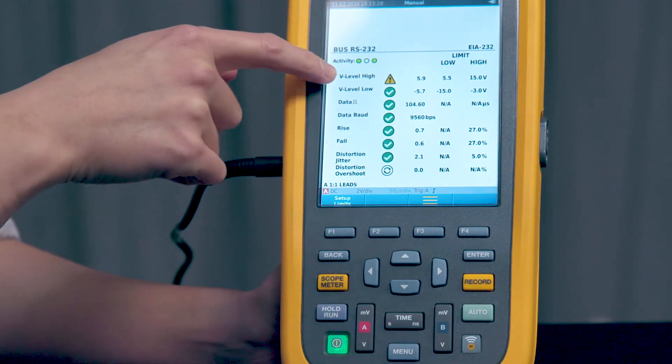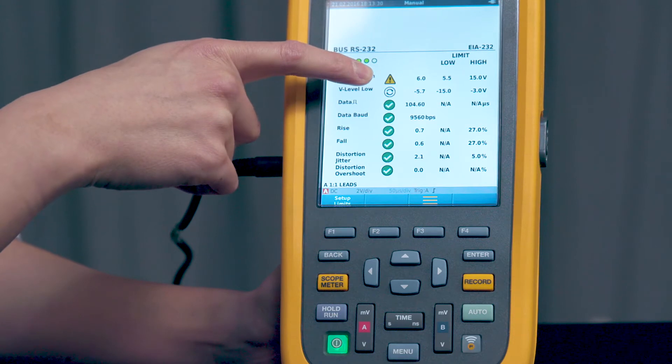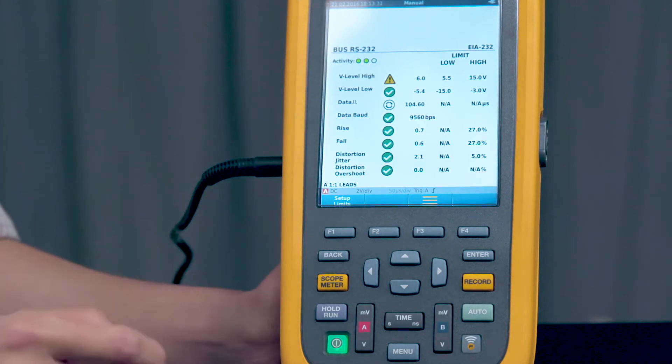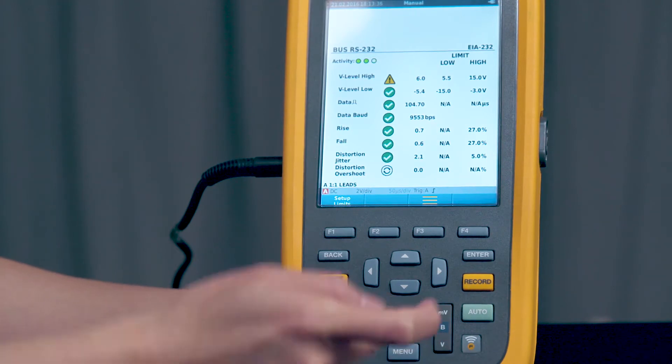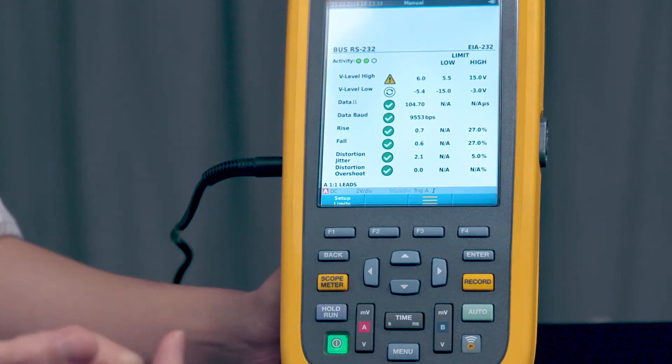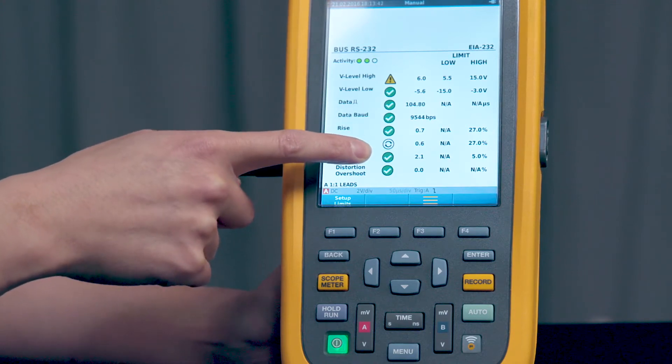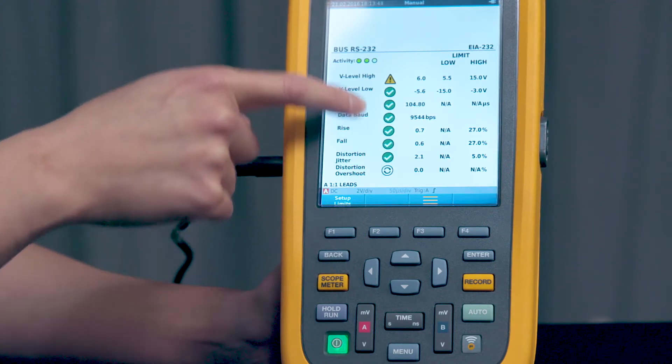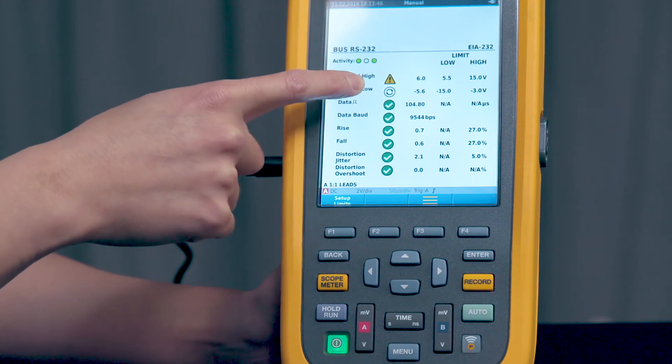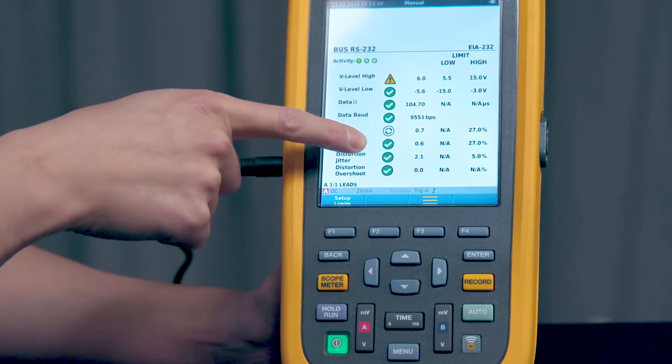You'll notice here VLevelHigh shows an exclamation mark. That means that the reading is between 80 to 100% of the allowable range. And if it's got a check mark, then your reading is okay. You also notice that the cycle symbol is appearing next to each test. That indicates which test it's executing right at that moment.